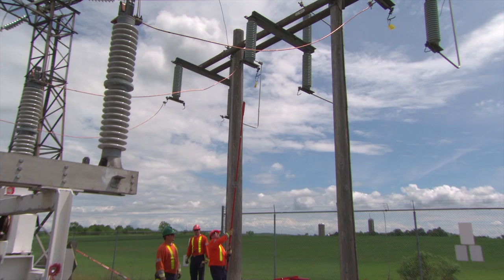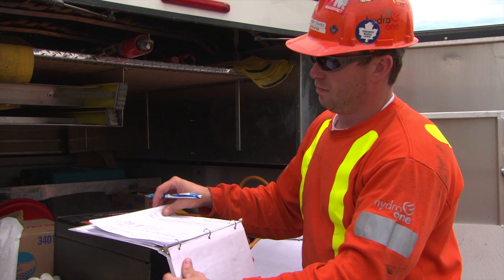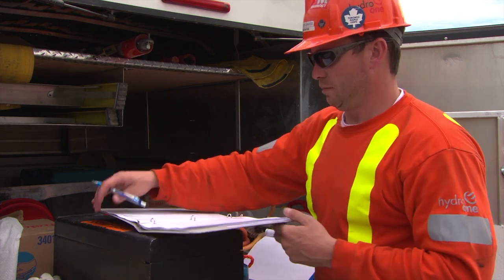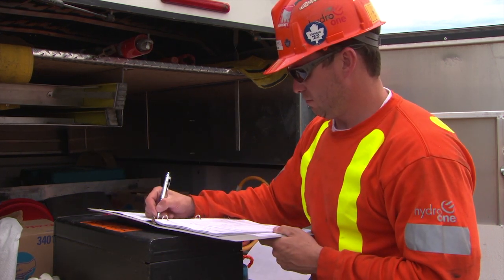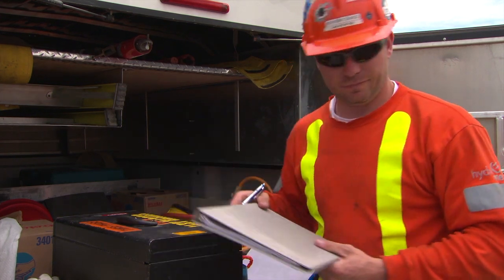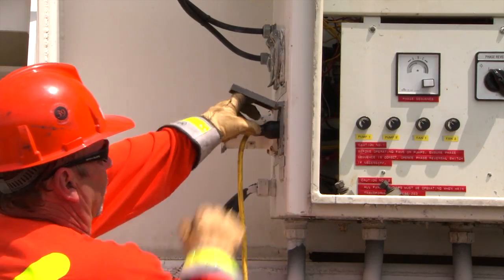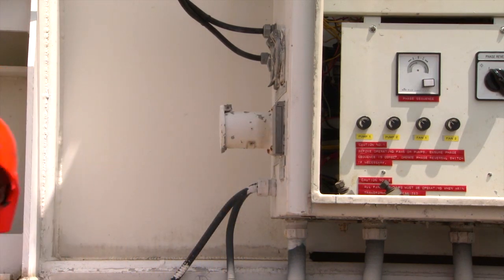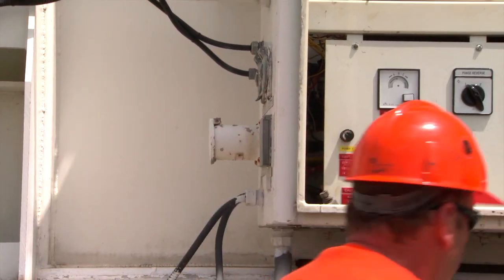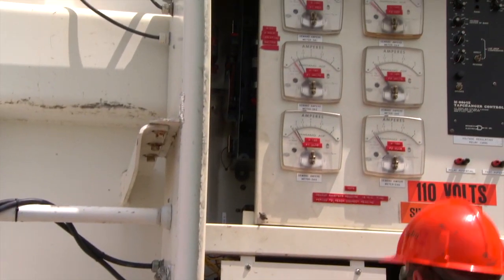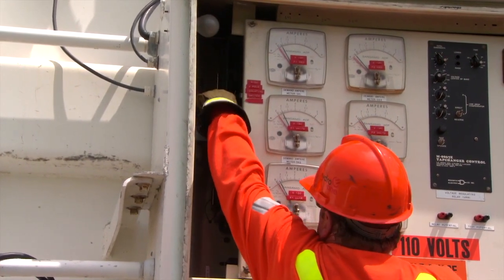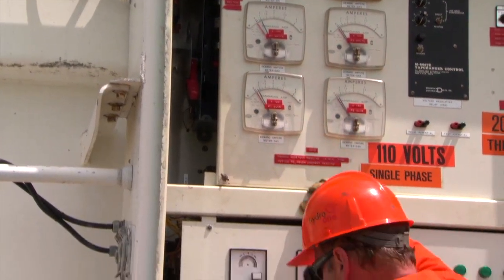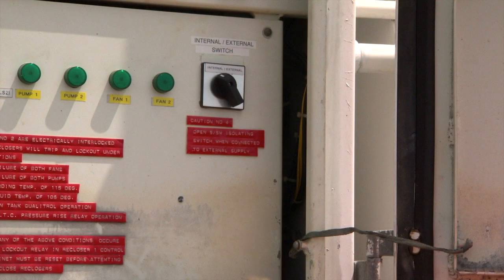Once the high-voltage connections are made, you must energize the MUS to verify that the reclosers are open. Prepare and check an OTO for removing the work protection tags, energizing the MUS, and verifying that the reclosers are open with the springs discharged. Check that the external supply is disconnected. Close the fused disconnect isolating switch located in the mech box of the MUS. Check that the internal-external switch is set to internal.